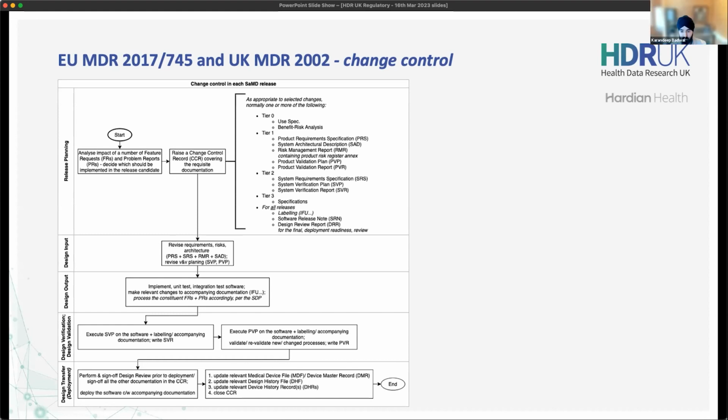And the last one from Berner, so yeah, interface customization like colors and logos. In most cases, the answer is no, unless of course, you've got to look at other factors. Let's just say something like maybe your users are colorblind. In that case, if you start using different colors, it may change the way they interface with it. So in most cases, no, but there are some cases in which it may be considered a substantial change. Yeah, or a tier 1 change at least. It's not really changed intended purpose, but it's a change that requires revalidation. Can your users actually cope with the color combinations?